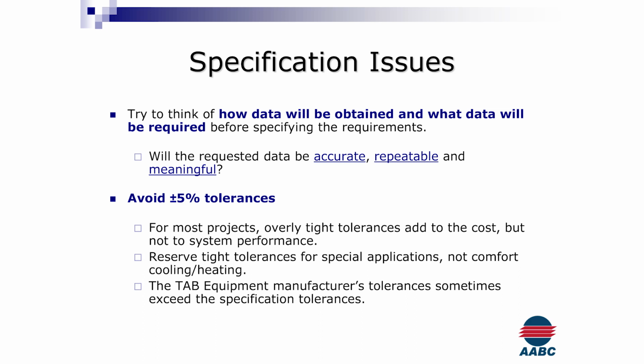Again, the 5% tolerance is there - that one drives me nuts. It's very hard to attain, and that can add time to the project. For TAB firms actually out there doing the work, we have to make 2, 3, possibly 4 passes before we can go through the entire system and try to read every outlet at 5%. Because as we're pushing air around, that 1% could be 1 or 2 CFM in a closet somewhere, and now we can no longer reach that 5% spec, because in some cases our instruments, even the manometers we're using, have tolerance and repeatability levels that can actually go against what's in the design, as far as the tolerances of the equipment we're using - VAVs in this case that can wander 14% either way.